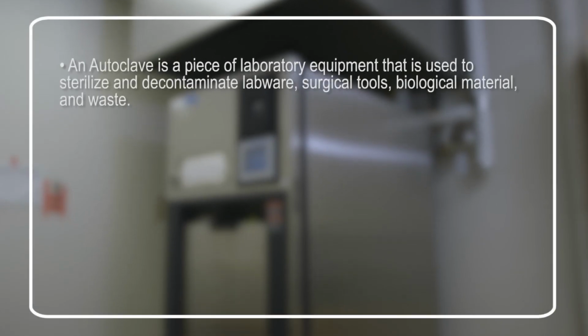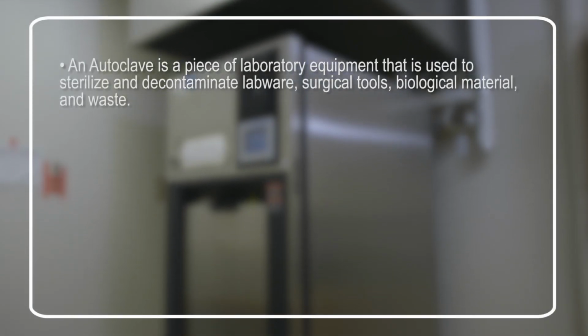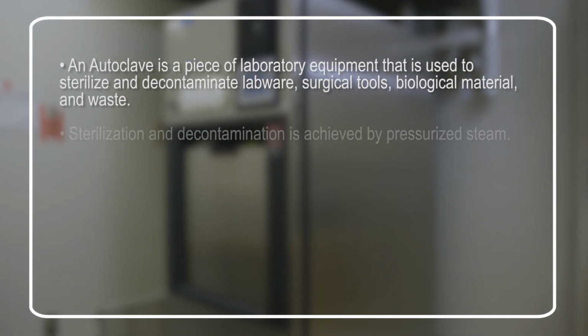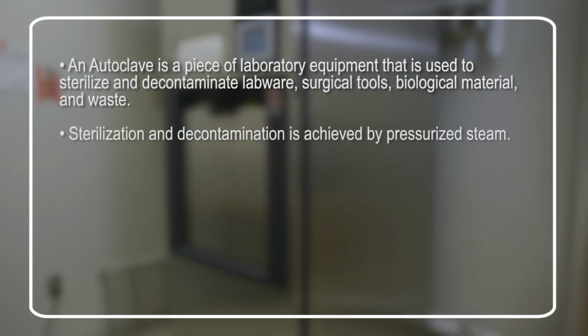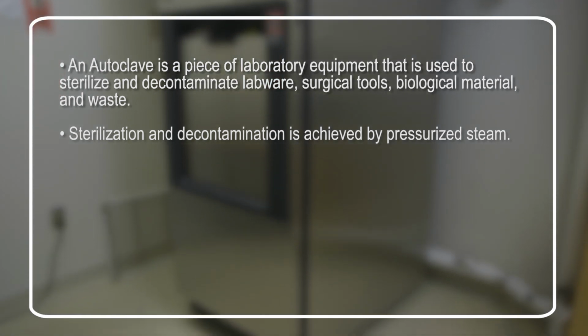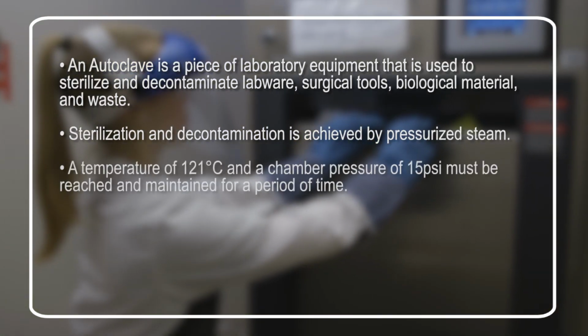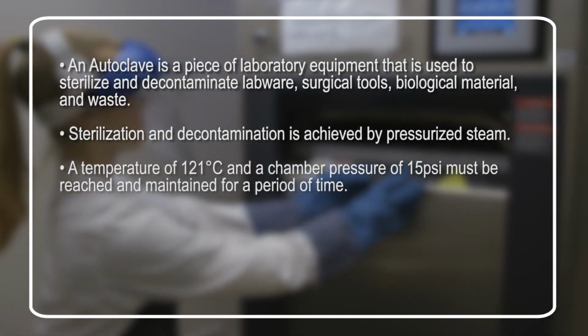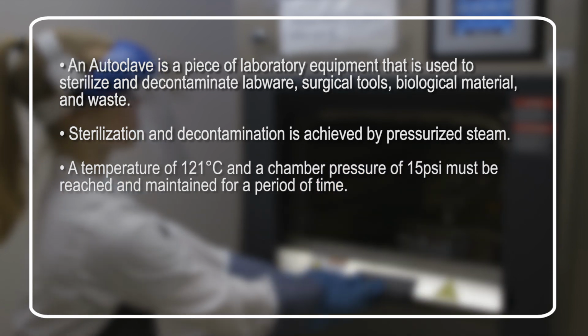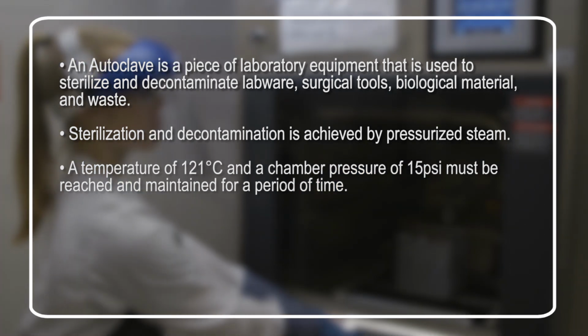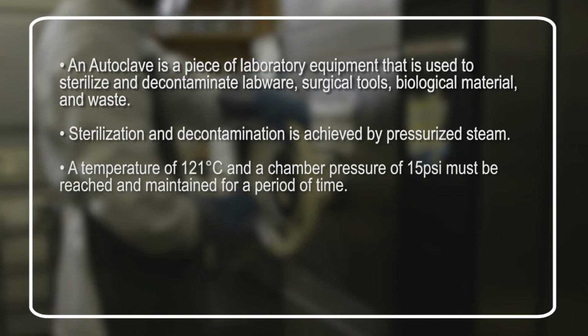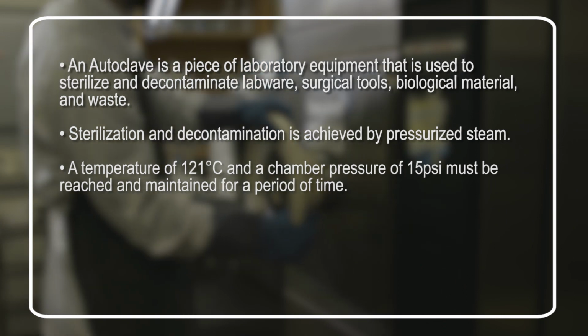An autoclave is a piece of laboratory equipment that is used to sterilize and decontaminate labware, surgical tools, biological material, and waste. Sterilization and decontamination is achieved by using highly pressurized steam to eliminate biological contamination from the items loaded into the chamber of the autoclave. A temperature of 121 degrees Celsius and a chamber pressure of 15 psi must be reached and maintained for a period of time to safely sterilize and decontaminate items within the autoclave chamber.